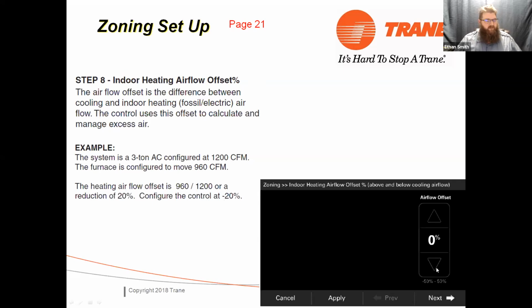Now, the general rules of thumb: if you have a 2-ton AC and a 60,000 BTU furnace, those line up almost perfectly, no airflow offset. 3-ton AC, 80,000 BTU furnace, same thing. 4-ton AC, 100,000 BTU furnace, you guys get the picture. Okay, but be aware of this. We run into this quite a bit. And across our footprint, we have dramatically different loads. The guys up in Breckenridge, Colorado, are putting in 120,000 BTU furnaces with 2-ton ACs. Okay, we've got big airflow offsets there. The guys down in New Mexico, they don't know what a gas furnace is in some places. So they may have a huge AC and a tiny furnace. It happens. So make sure that you're setting your airflow offsets accordingly.